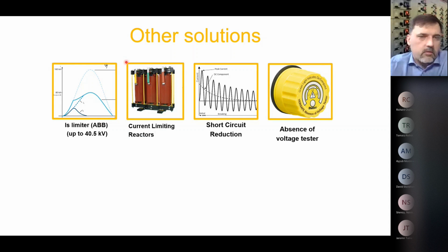It's a specific topic to check, but it's not that if you install it, it will solve your problems. It might be used as a solution to lower the energy at some point, but you need to check it. Short circuit reduction, I have it separated because it means that you might configure your system a different way. Instead of operating 2 or 3 parallel transformers, you might operate 1 or do it a little bit differently, split your loads. And absence of voltage tester.